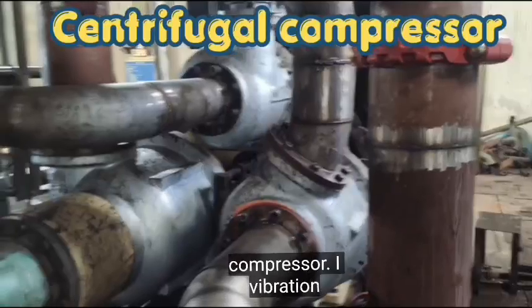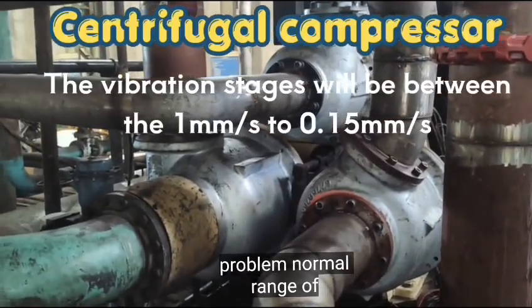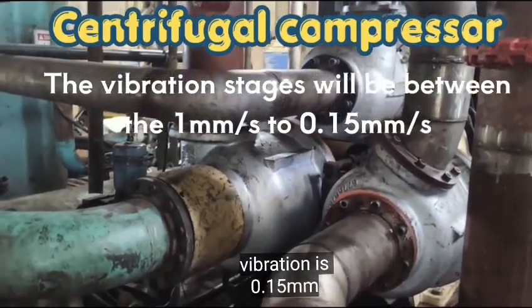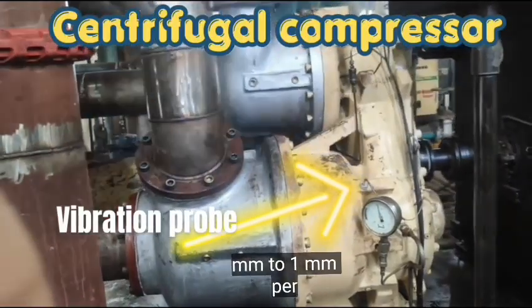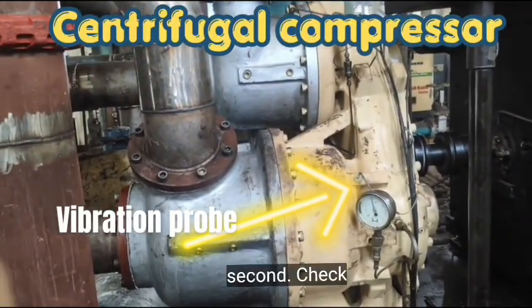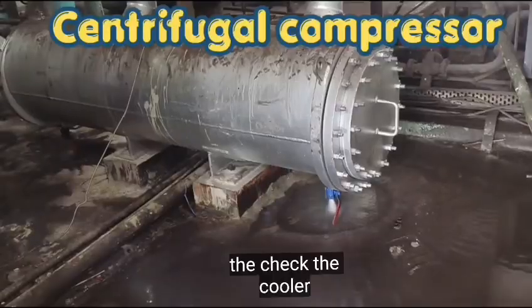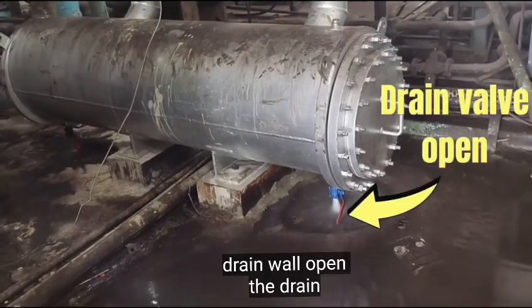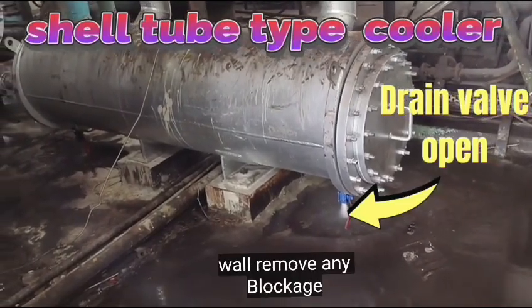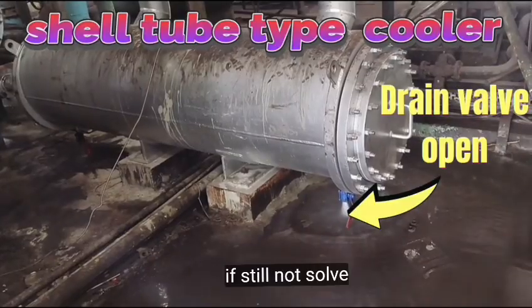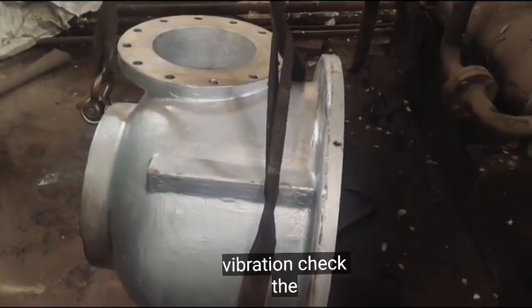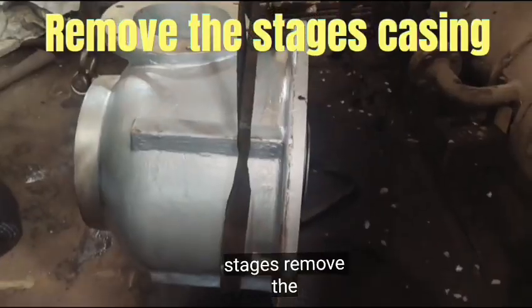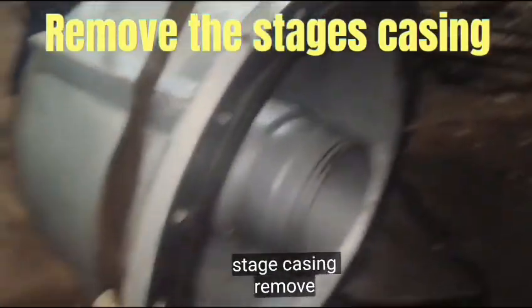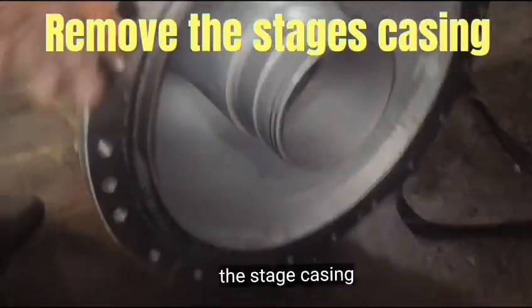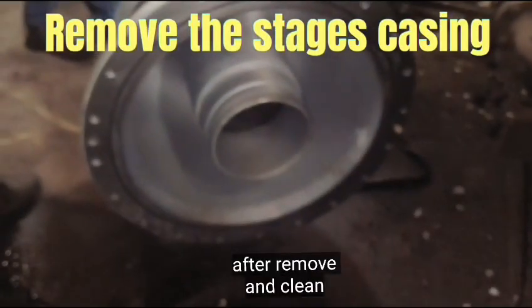Centrifugal compressor high vibration problem. Normal range of vibration is 0.15 mm to 1 mm per second. Check that the cooler drain valve is open. Remove any blockage from the drain valve. If the vibration is still not resolved, check the stages. Remove the stage casing.